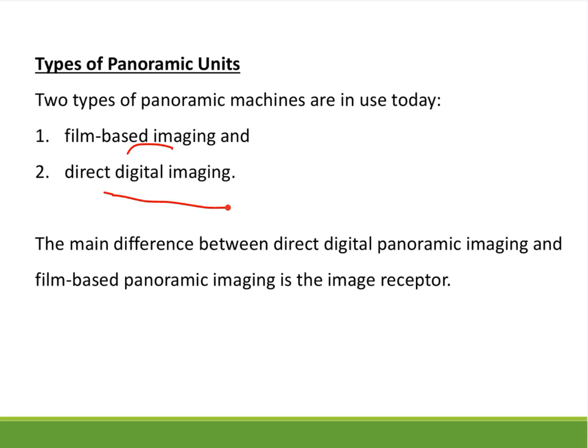In direct digital imaging, as soon as you take the exposure you see the image on the display. In indirect imaging, you need to scan the image sensors or receptors before you can see an image. We have two types of panoramic units: film-based and direct digital, which can be CMOS, CCD, or a flat panel. The main difference is the image receptor — one uses film, the other uses a sensor.